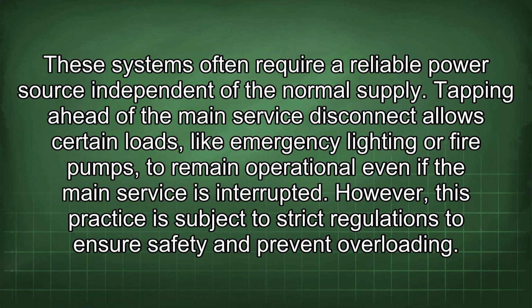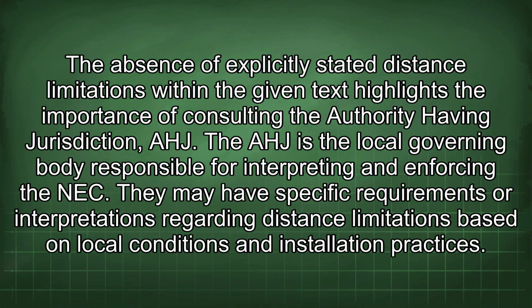Tapping ahead of the main service disconnect allows certain loads, like emergency lighting or fire pumps, to remain operational even if the main service is interrupted. However, this practice is subject to strict regulations to ensure safety and prevent overloading. The absence of explicitly stated distance limitations within the given text highlights the importance of consulting the authority having jurisdiction (AHJ). The AHJ is the local governing body responsible for interpreting and enforcing the NEC. They may have specific requirements or interpretations regarding distance limitations based on local conditions and installation practices.